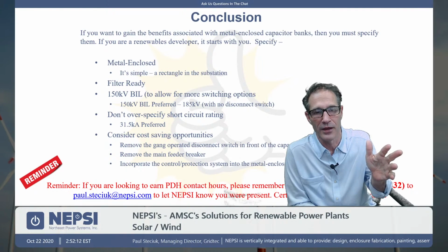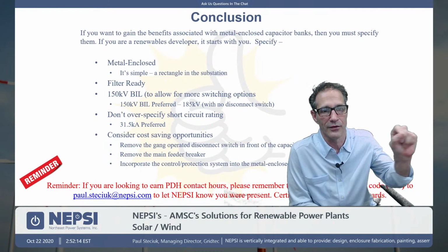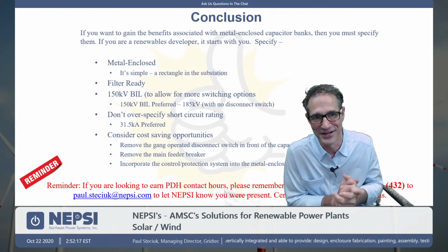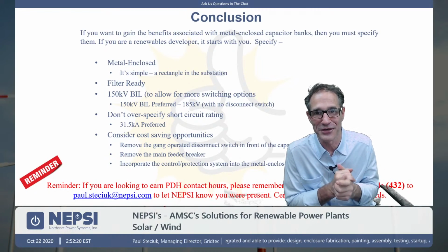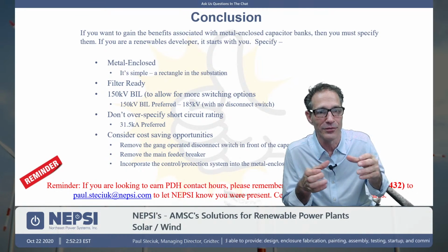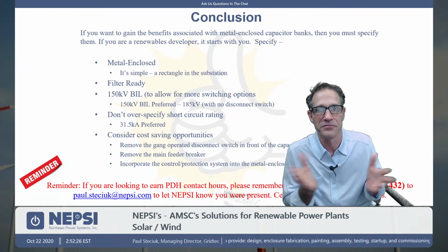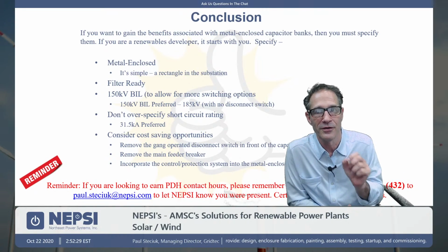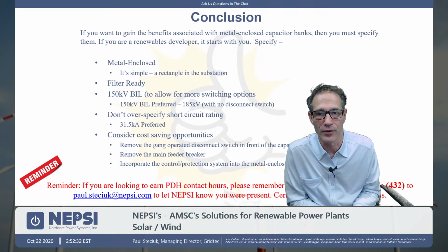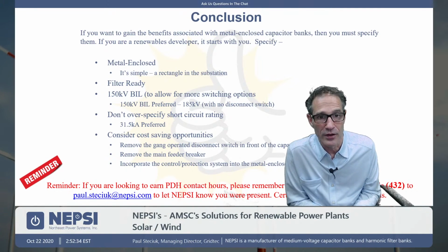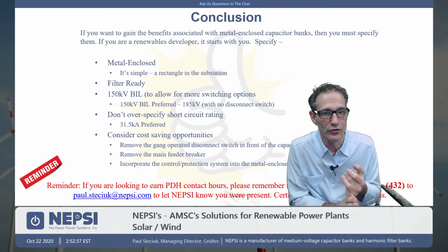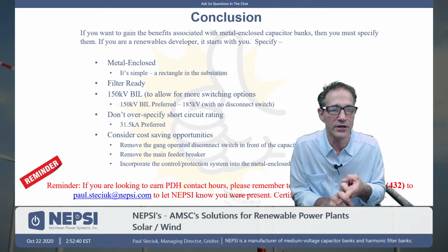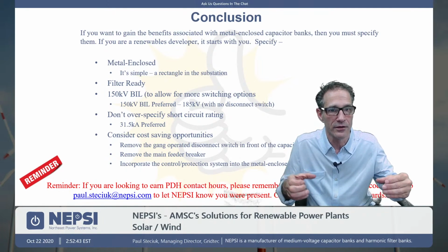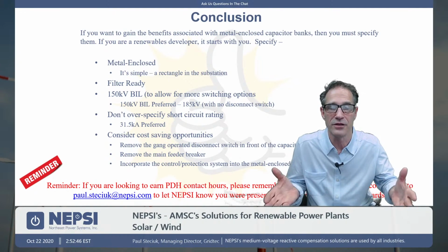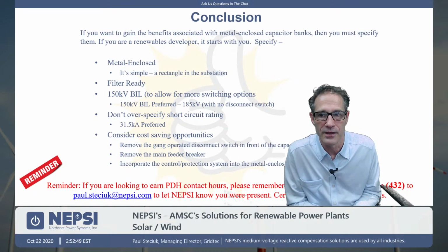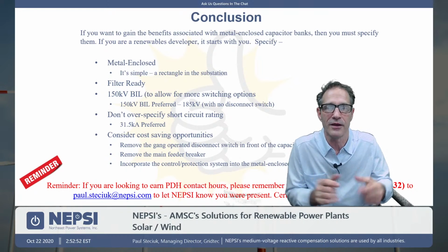If the size of the bank increases in rating, make the rectangle a little bit longer. It's very easy. I can't stress how easy it is. Inside that rectangle will be everything, but from your drawing standpoint, that's all you need. So a specified metal-enclosed, it's only a rectangle in the substation from your standpoint. We have a standardized drawing set, basically saying if I need a 2-stage, a 3-stage, a 4-stage, how many megavars you need, you can get a budgetary length for the size of that rectangle. So send us an email, ask for that template of coming up with the size of the rectangle, and we will give that to you.